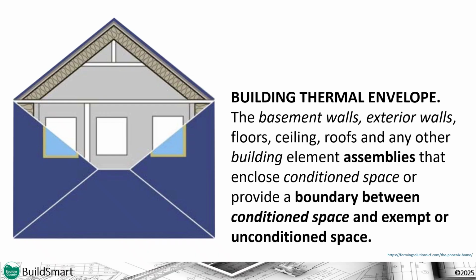Section N1106.2.1 Interior Design Conditions states that the interior design temperature used for heating and cooling load calculations shall be a maximum of 72 degrees for heating and a minimum of 75 degrees for cooling. See Table R301.2 and Section N1101.9.1 Exterior design conditions, which state that the exterior design conditions shall be based on climate data for locations, since Boulder County is a jurisdiction that spans a large elevation range from the plains as well as up into the mountains.